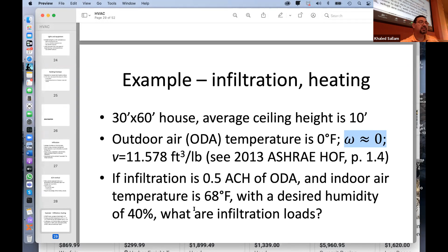The infiltration load at this time would be a heating load. Very cold air comes in, and you're supposed to heat it up to 68. So he's calculating the total volume, then taking only 0.5 of it, and adding it per hour because it's air changes per hour. That's important to remember, we assume this is happening per hour.